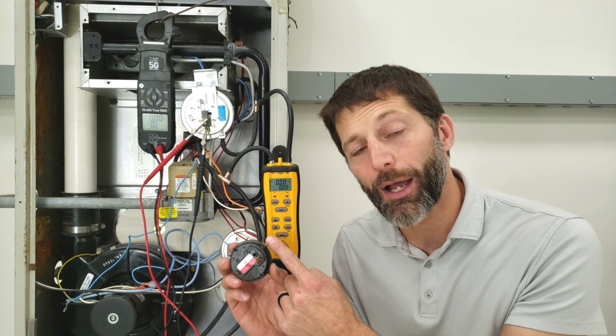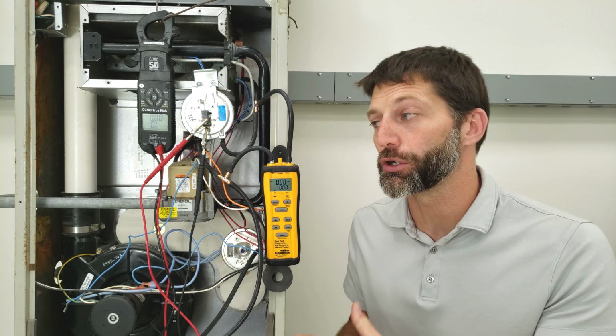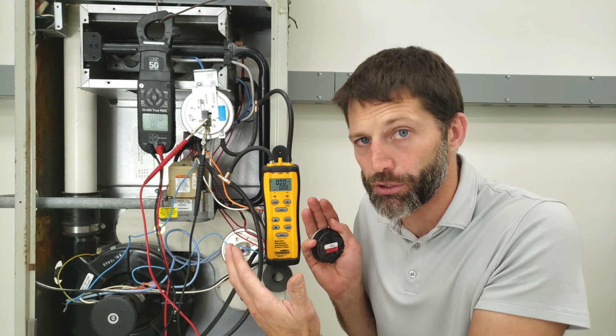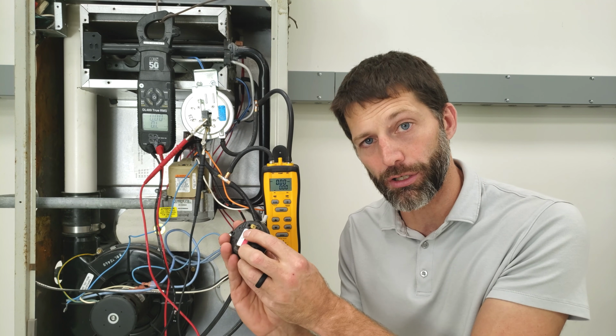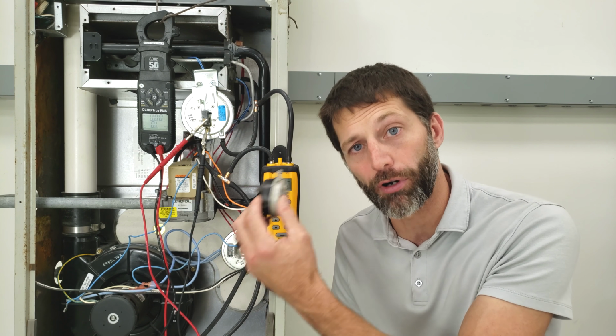So remember that anytime you're measuring pressure on a pressure switch, you're not really measuring negative pressure. You're measuring a pressure reduction or a pressure differential across the switch.